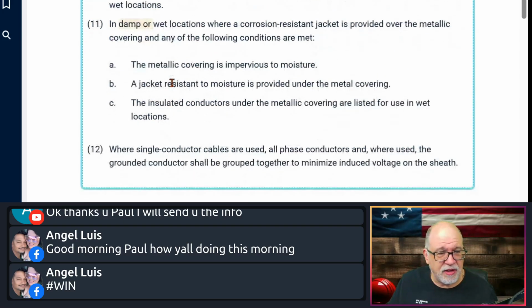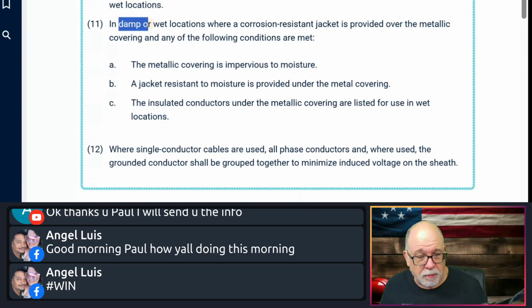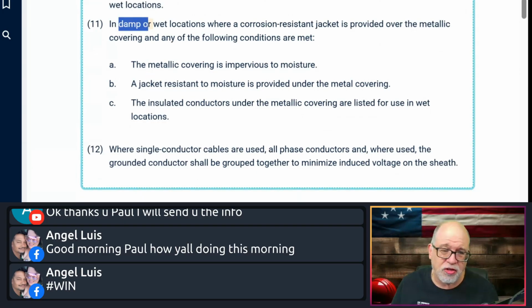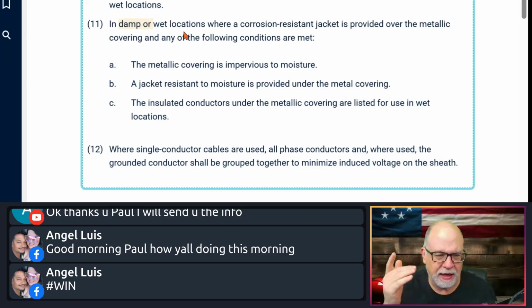Next, it says 11. And you see this right here where it says damp. That was my public input, only from a wiring cable perspective. Nothing in the standard UL 1569 talks about damp, but it does talk about wet. And if it's wet, damp is just a lesser restriction. It is anything but dry, right? So you have the same issues. So I wanted to make it clear that if you're going to use metal-clad cable, and again, one of the most popular wiring methods in the world, in a wet or damp location, it's got to be constructed a little differently.